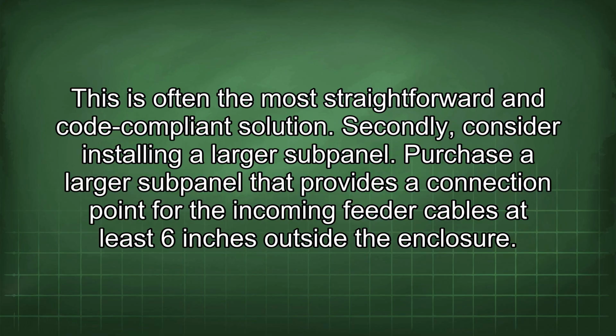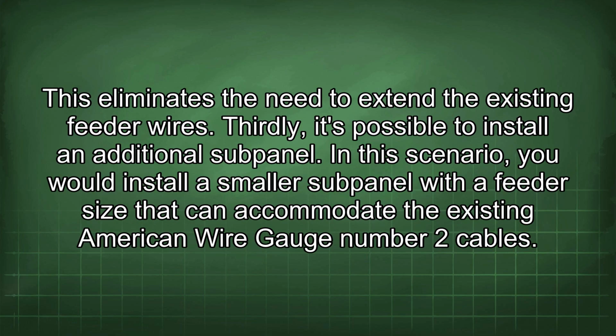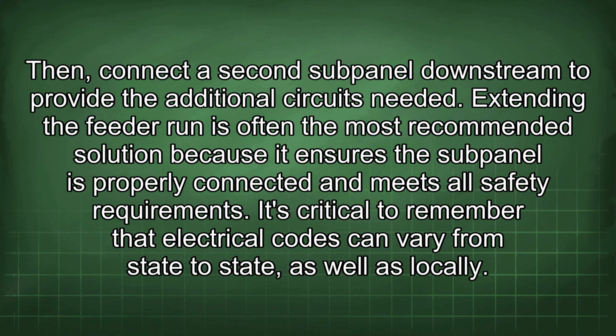Secondly, consider installing a larger subpanel. Purchase a larger subpanel that provides a connection point for the incoming feeder cables at least 6 inches outside the enclosure. This eliminates the need to extend the existing feeder wires. Thirdly, it's possible to install an additional subpanel. In this scenario, you would install a smaller subpanel with the feeder size that can accommodate the existing American wire gauge number 2 cables. Then connect a second subpanel downstream to provide the additional circuits needed.